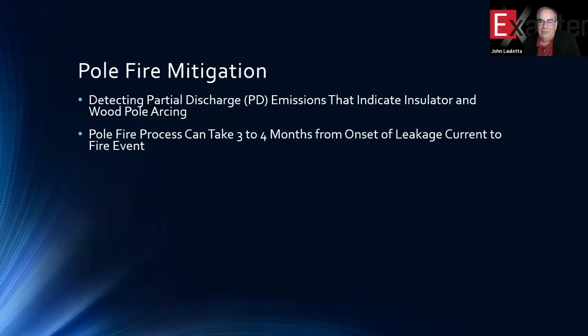We look at pole fires as taking about 3 or 4 months from the onset of leakage currents to the event occurring. And the event occurring may come at those high humidity times or wet times, but it's been going on for some time. And you'll see that when you take the pole apart, if you can, if it's not burnt completely, you can see where at the bolts there's charcoal just basically building up as the pole begins to participate in the process.